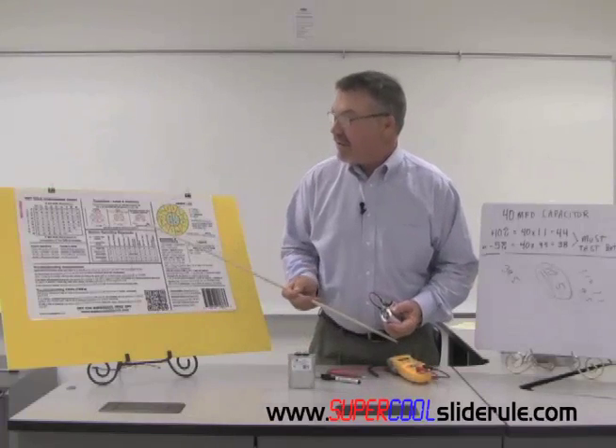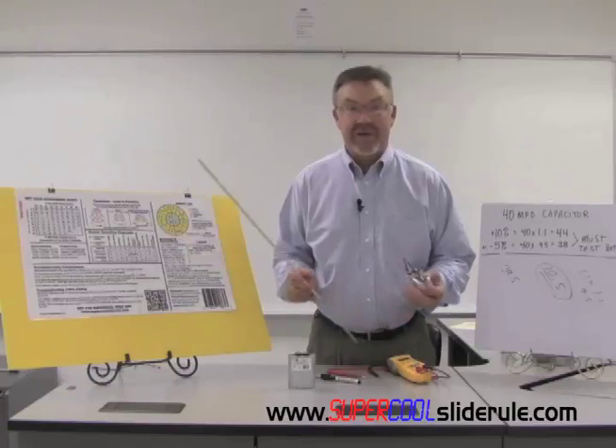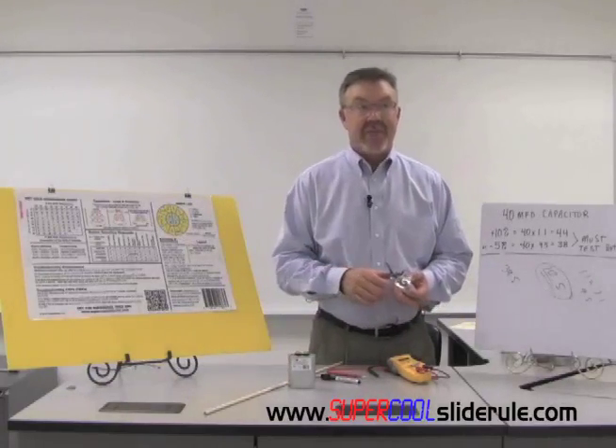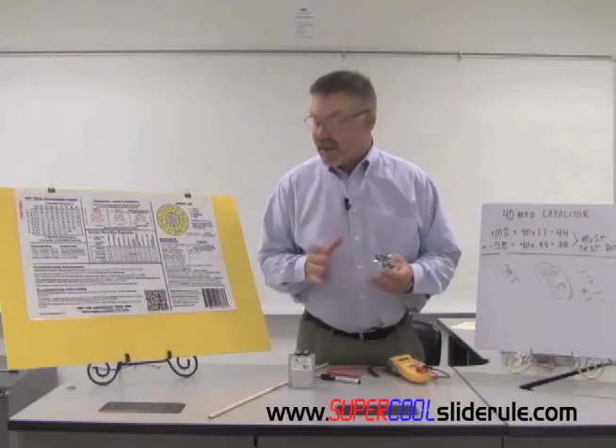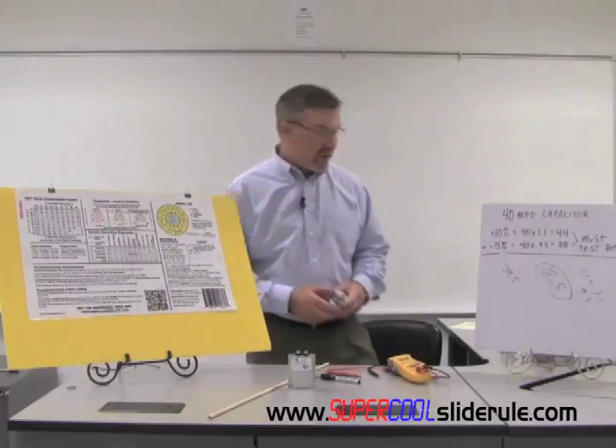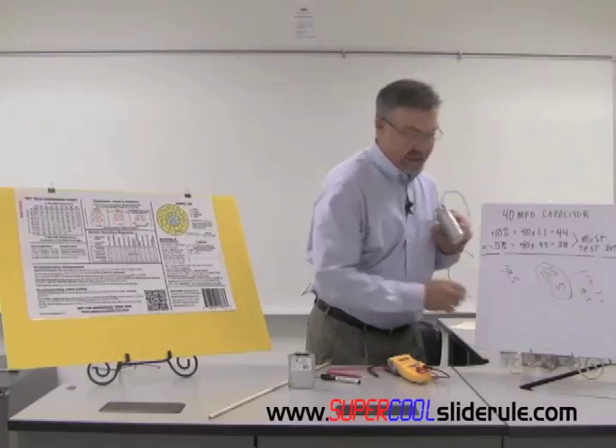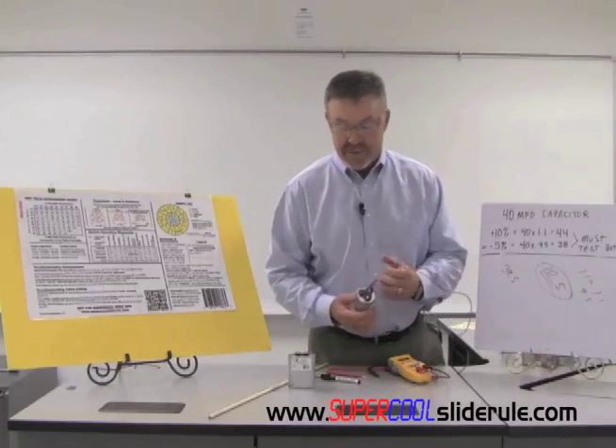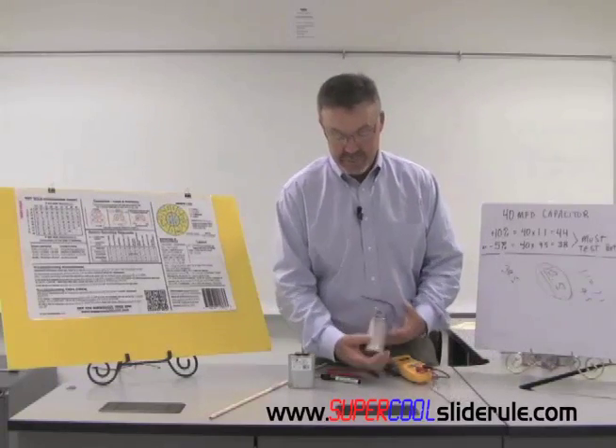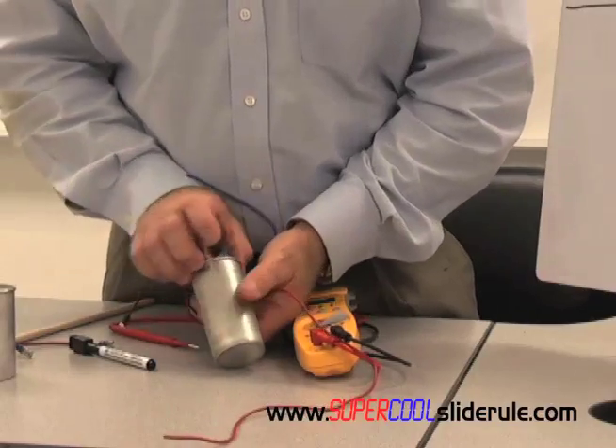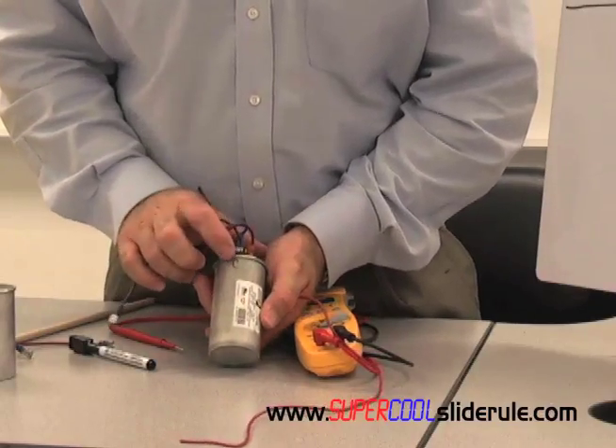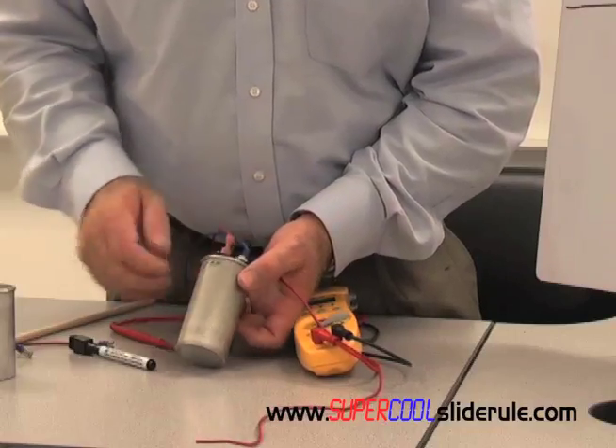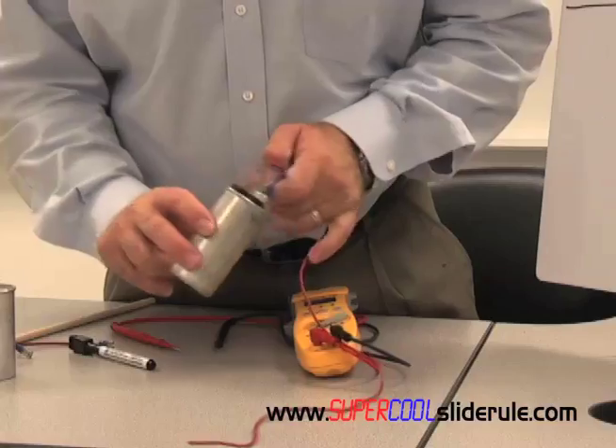Last but not least, you're running this all the time. You're out in the field, you need a dual run capacitor. All you have is a lot of single capacitors. So this is going to represent our dual run capacitor, and it's blown. Here's my Herm, here's my fan, and over here is my common. Okay, so this one is blown.